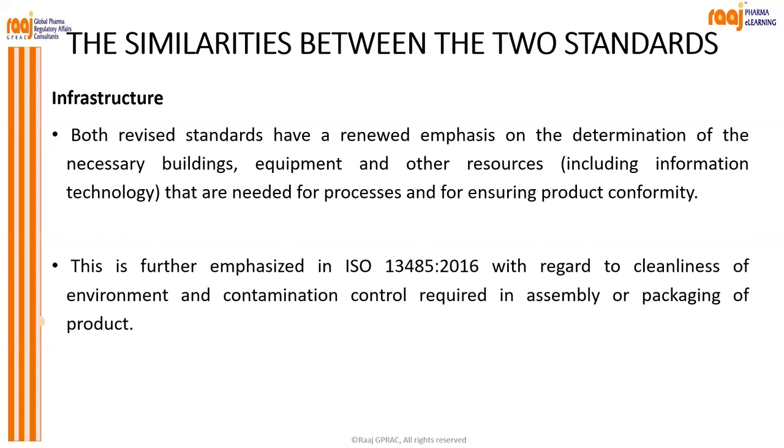So CSV becomes very important when we go for the automated system. So you have to see the ISPE standard, that is GAMP. GAMP is good automated manufacturing practice, and you have to follow those good automated manufacturing processes as defined by the applicable regulatory requirement. So when we are talking about the USFDA requirement, we have to follow 21 CFR Part 820, that is QSR, the Quality System Regulation, which is defined as per the CFR, Code of Federal Regulations, 820.